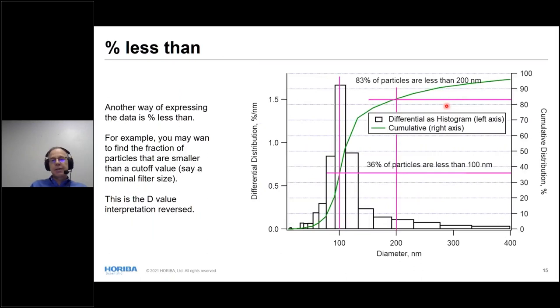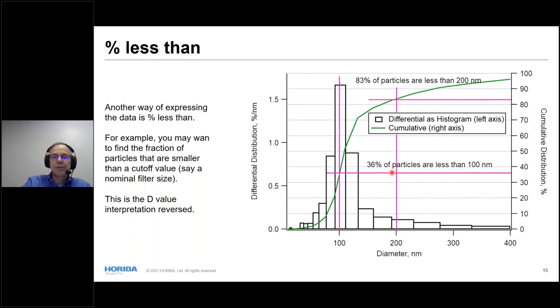You can also turn this around: if you have a process concern, say filtration, you start at a particular size on the cumulative and read off the percentage. For example, 83% of particles are less than 200 nanometers, or 36% are less than 100 nanometers. If there's a size cutoff you worry about, you look for values of 'percent less than,' and one minus that is 'percent greater than.' This is really D-value interpretation reversed.